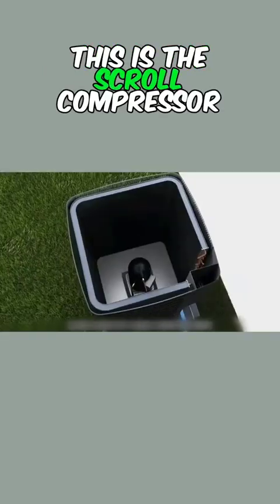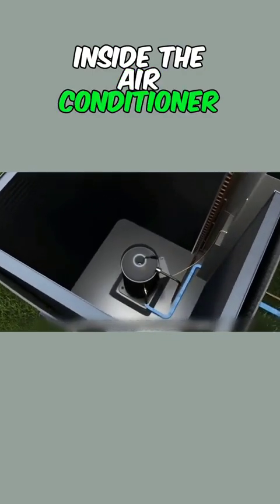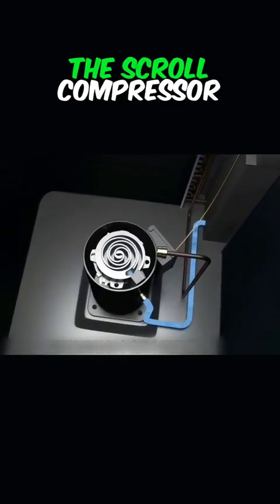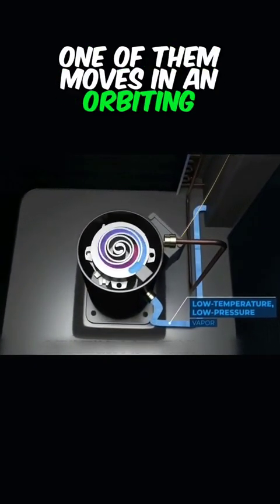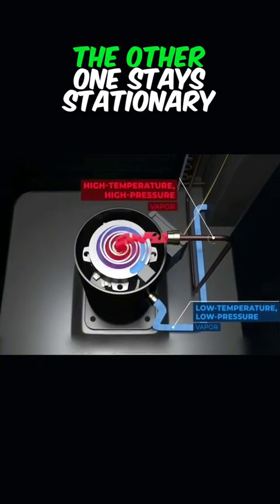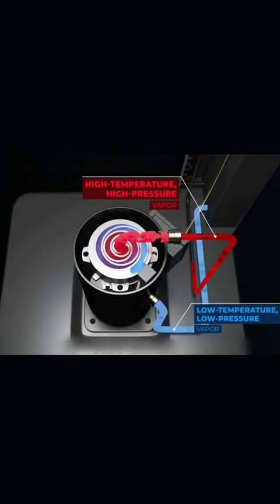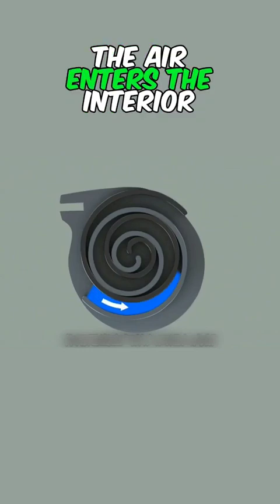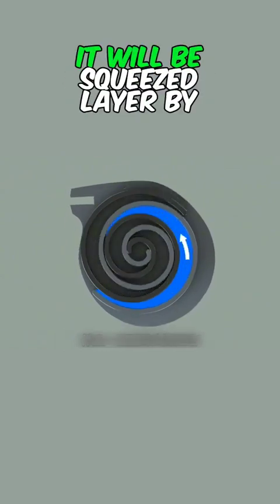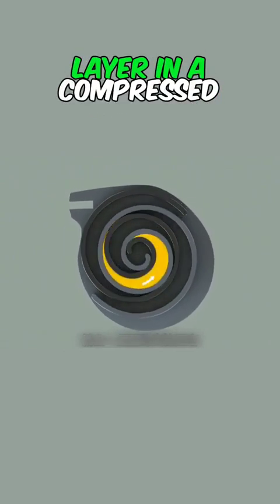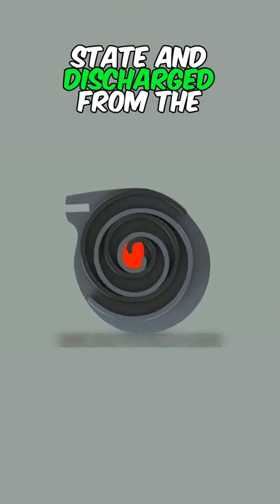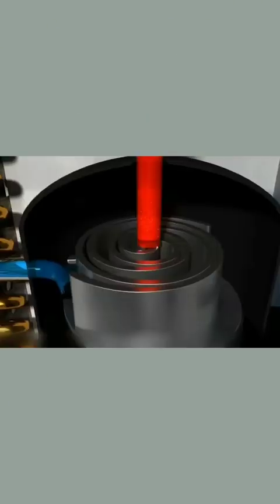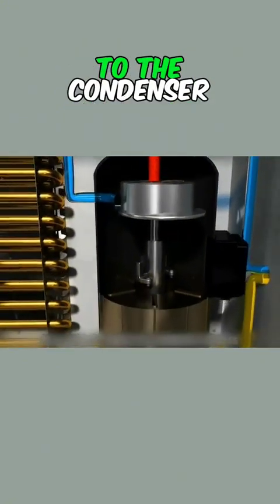This is the scroll compressor inside the air conditioner. There are two main parts in the scroll compressor. One of them moves in an orbiting pattern but does not rotate. The other one stays stationary. The function is that when the air enters the interior from the inlet, it will be squeezed layer by layer in a compressed state and discharged from the middle of the vortex. Then the compressed air is sent to the condenser.